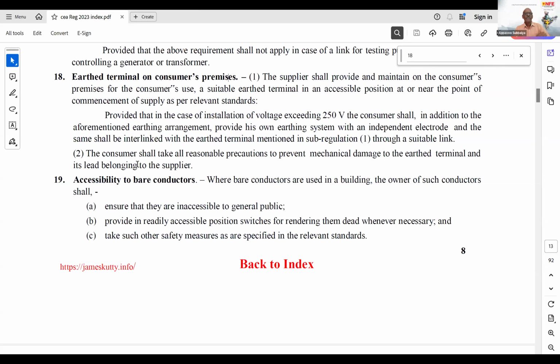Yes. Thank you, Mr. Manuji. Actually, it's a concern for frequent sensitive electronics, because most of the domestic premises are now flooded with power electronics devices, whether it's a laptop or LED TV or LED lamps, all are sensitive to overvoltages. Also, for such overvoltage, the consumer's gears or protective gears won't work because it is a fault from outside of the premises. So my view regarding this is, first we have to make the supplier's installation compliant to the code before insisting the consumer to connect his terminal to the supplier. The supplier terminal has to be safe to connect. So yes, without this, this regulation will be difficult to enforce.